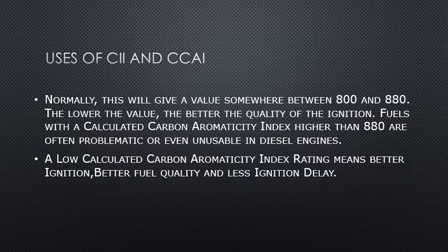Moving on further, that is the uses of CII and CCAI. Normally this gives a value somewhere between 800 to 880. So the lower the value, the better the quality of the fuel. The fuels which have a CCAI higher than 880 are very problematic, and we are unable to use them in the diesel engines. They are of no use basically. So a low calculated carbon aromaticity index rating means better ignition, better fuel quality, and less ignition delay.